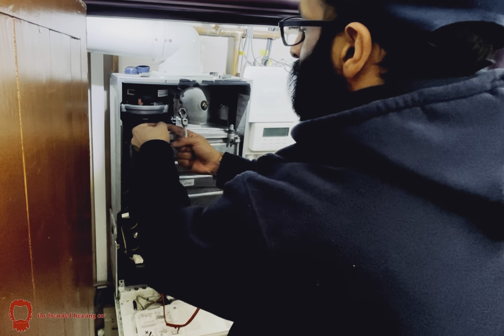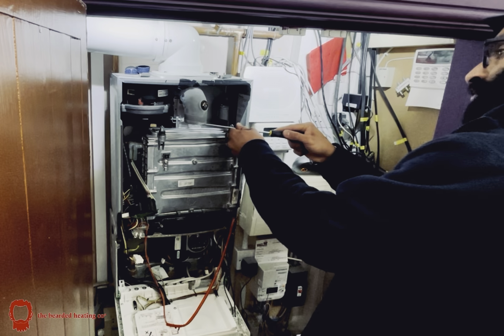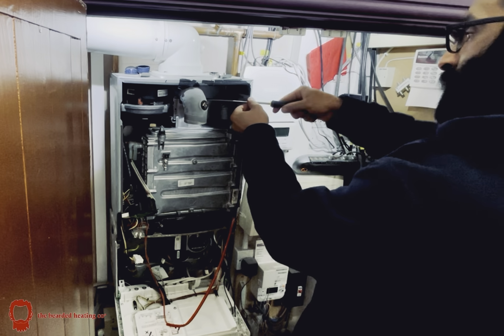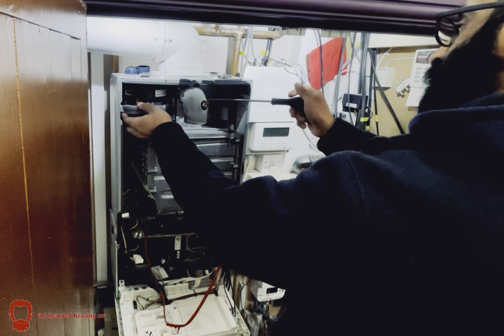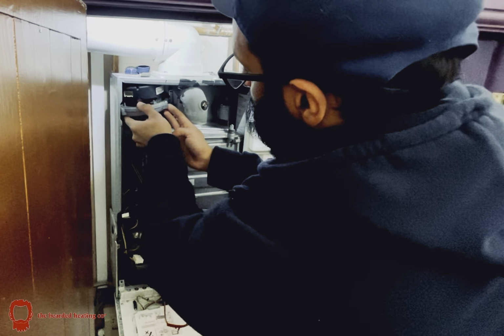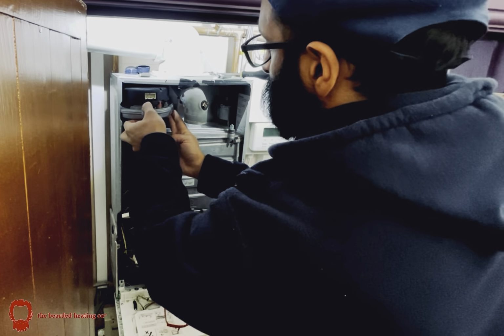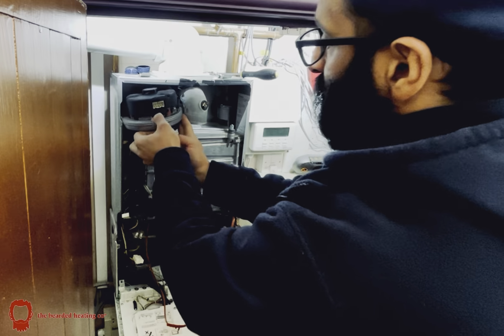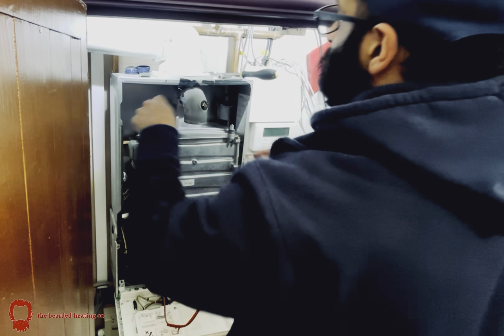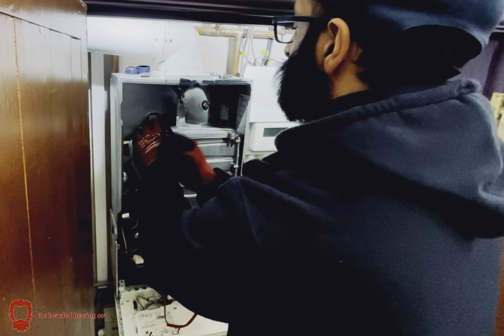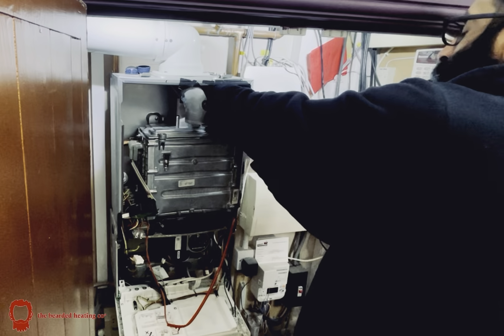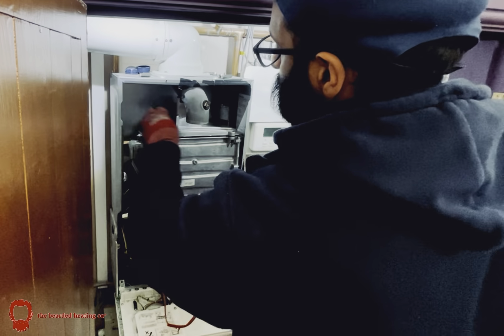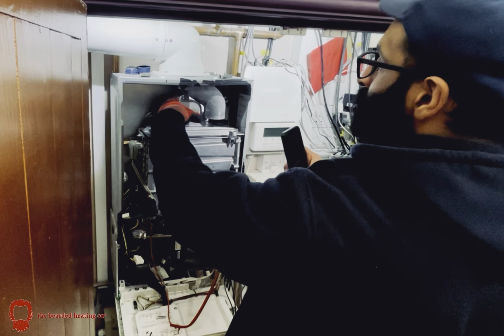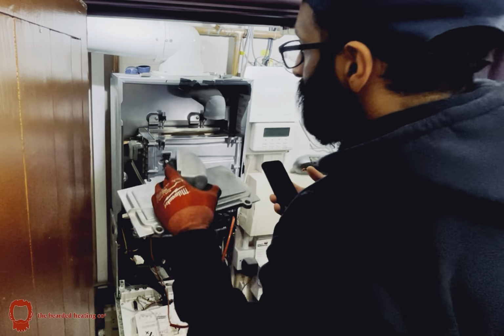Then using a 10mm ratchet, I undo the bolts holding the burner in place. Remove the fan. It's a bit tight, but it all comes out. It's not a bad boiler to work on. People make it out that it's really tight and really awkward, but the reason I made this video was just to show you how easy it actually is to strip this boiler apart.